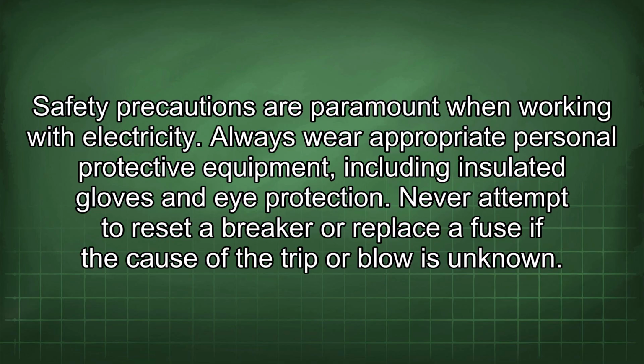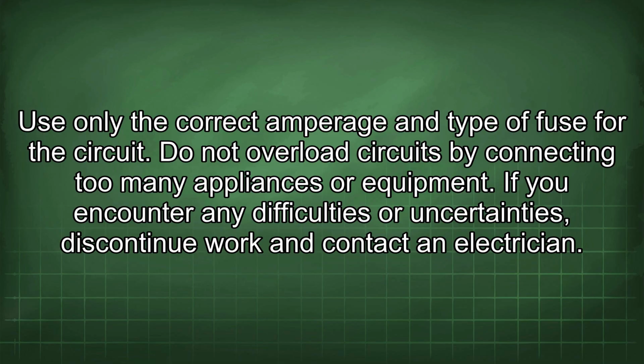Safety precautions are paramount when working with electricity. Always wear appropriate personal protective equipment, including insulated gloves and eye protection. Never attempt to reset a breaker or replace a fuse if the cause of the trip or blow is unknown. Use only the correct amperage and type of fuse for the circuit. Do not overload circuits by connecting too many appliances or equipment. If you encounter any difficulties or uncertainties, discontinue work and contact an electrician.